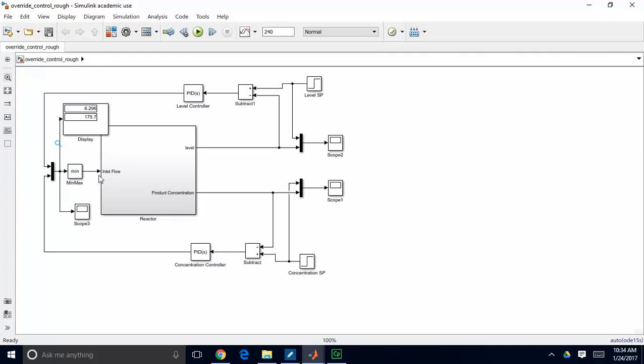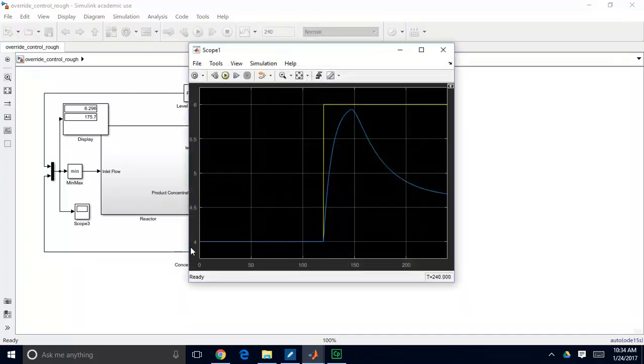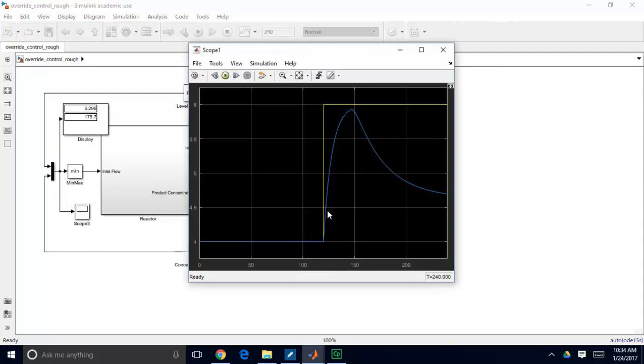The issue that we ran into was that, so initially we're controlling concentration. When we make a setpoint change in our concentration from 4 to 6, this concentration controller starts calling for more and more control. And it takes quite a while, but eventually our level controller overrides it and kicks in and tries to bring down the flow and bring down the level.